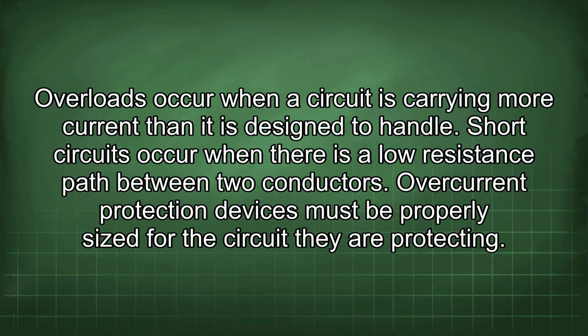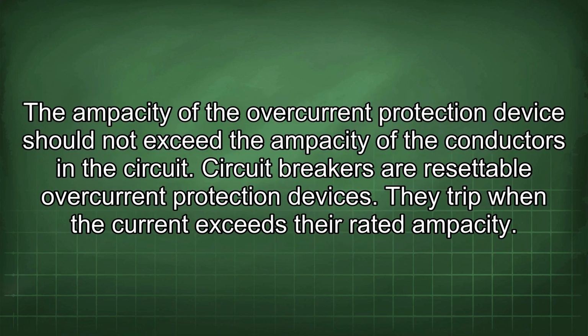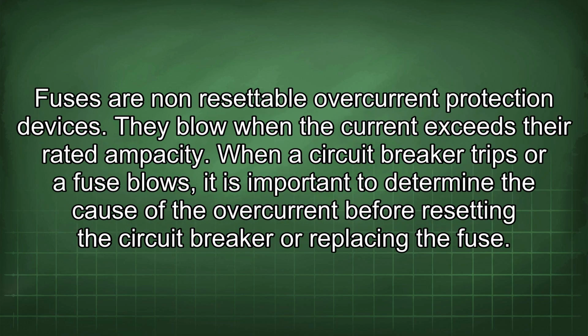Overcurrent protection devices must be properly sized for the circuit they are protecting. The ampacity of the overcurrent protection device should not exceed the ampacity of the conductors in the circuit. Circuit breakers are resettable overcurrent protection devices. They trip when the current exceeds their rated ampacity. Fuses are non-resettable overcurrent protection devices. They blow when the current exceeds their rated ampacity. When a circuit breaker trips or a fuse blows, it is important to determine the cause of the overcurrent before resetting the circuit breaker or replacing the fuse.